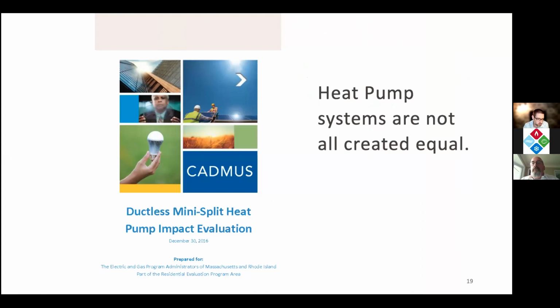Why go through all the trouble of a ground heat exchanger compared to, say, an electric resistance heater that's 100% efficient? You plug a resistance heater into the wall, you get one watt or one kilowatt of energy from the grid, and you get one watt or one kilowatt worth of heat into the house.